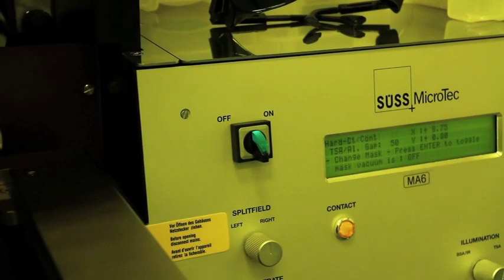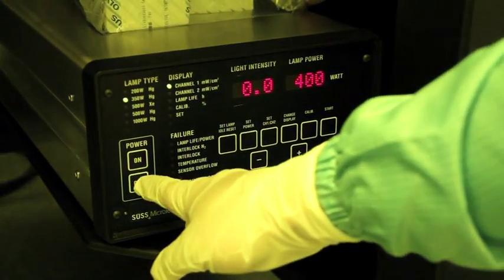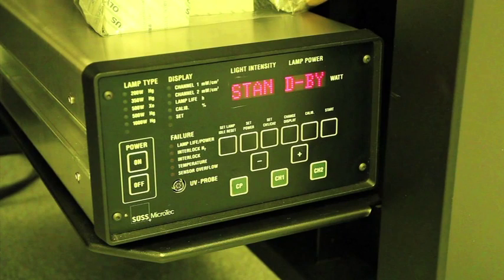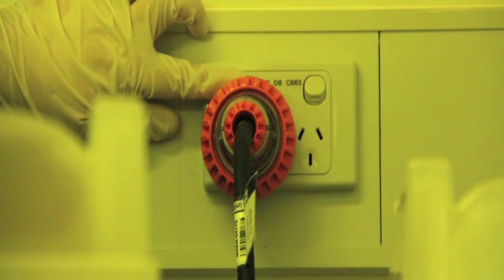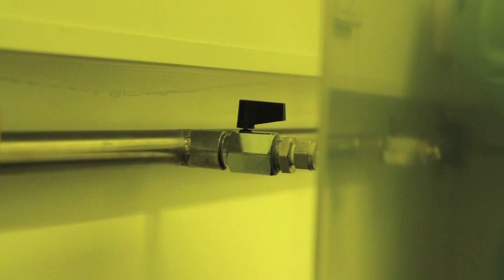Turn off the upper electric panel at the switch. Then press off on the lamp power supply. Be careful not to turn off the lamp directly after exposure. Wait for at least 10 minutes. In order to allow the system to cool down after operation, run the nitrogen for an extra 15 minutes prior to turning off the main switches and gases.